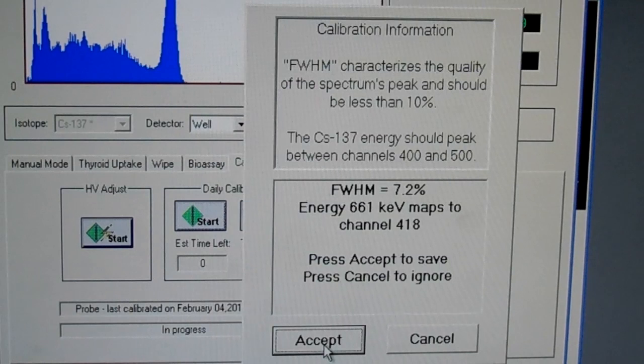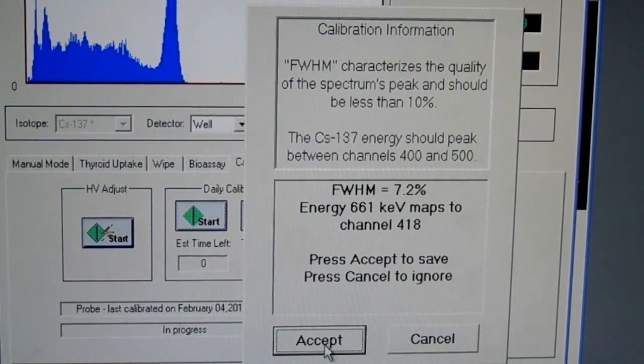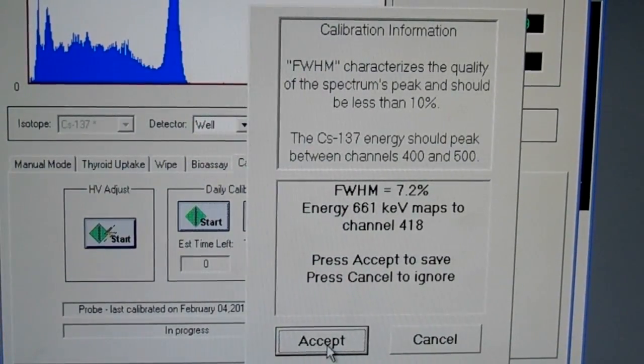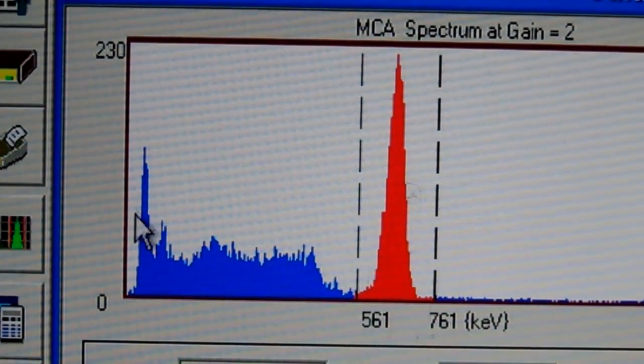It's explaining that the full width half max is within acceptable ranges and that the peak energy of the cesium checks out. So just explain that this screen tells you whether or not your equipment is in fact working or not. Now you're going to want to talk about the different radiations that we see in the graph.